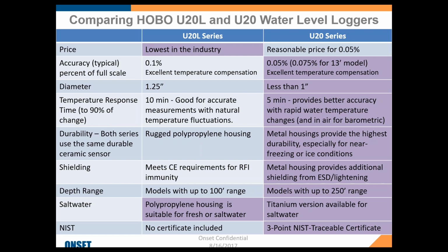There are several different ranges, and you choose based on the range you need to measure. We have up to 100 feet in the plastic polypropylene models, and up to 250 feet in the metal loggers. The shorter the range you're measuring, the slightly tighter the accuracy. You get a 3-point traceable certificate with every metal logger when we ship it. We don't provide certification for the U20Ls, but they're all under warranty to be within spec for 1 year, and both have a 5-year battery life.